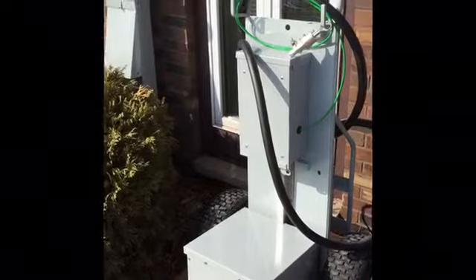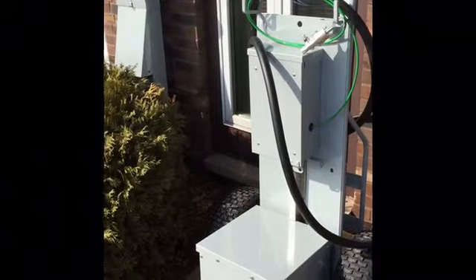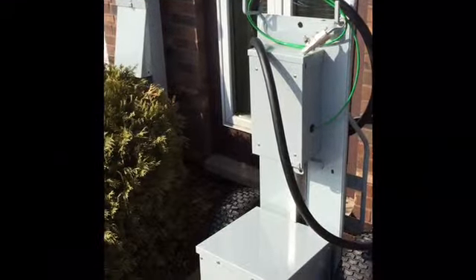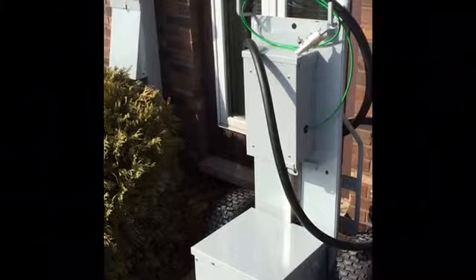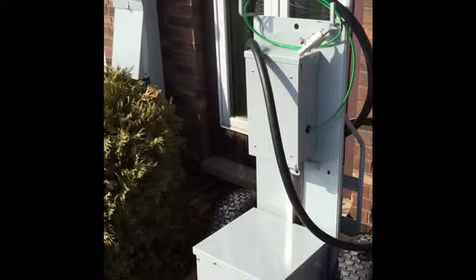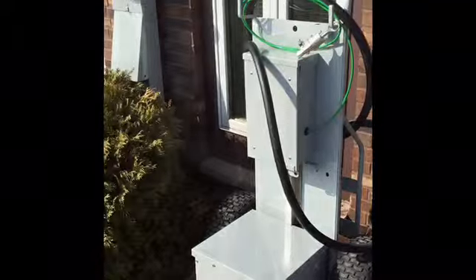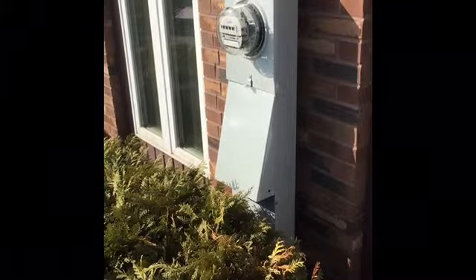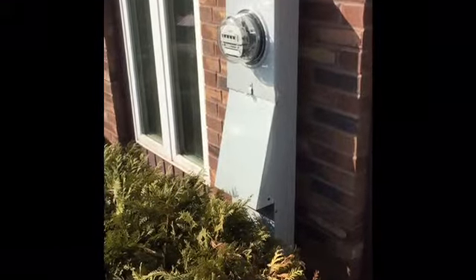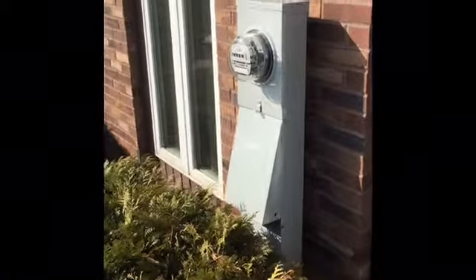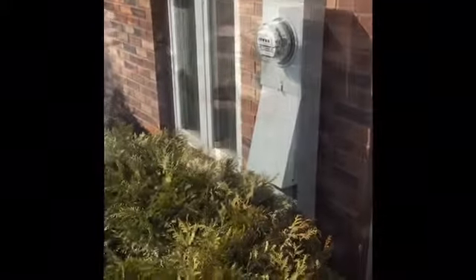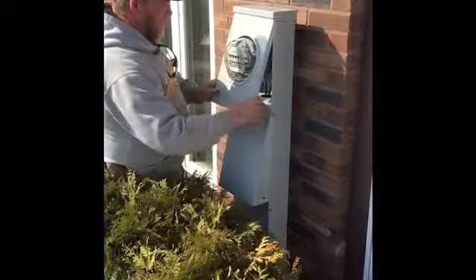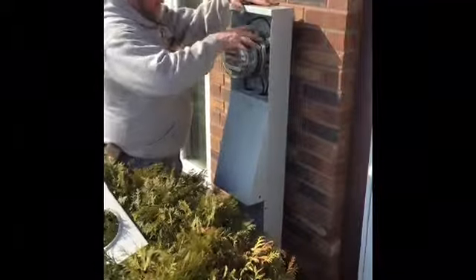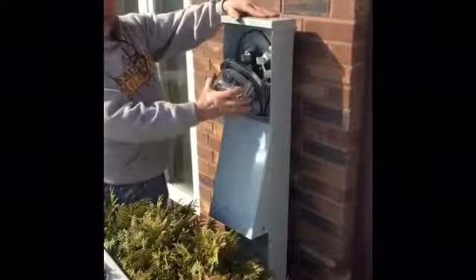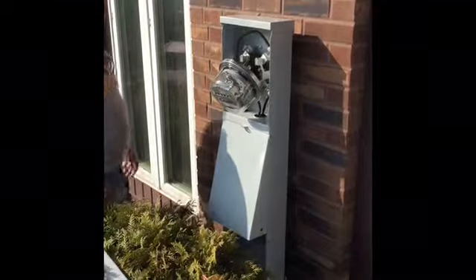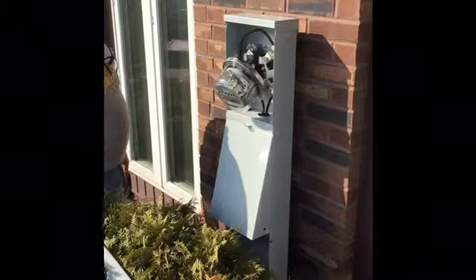So the first thing you do after bringing the cart up, get it within a few feet of the meter socket, is have your customer turn the breaker off on the inside. Okay, so then the first thing to do after you turn the customer's breaker off is to remove the meter out of the customer's meter socket. There we go. Got the meter cover off. Now we've got the meter coming out.